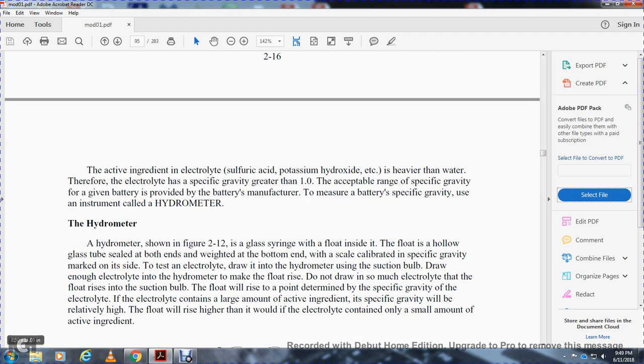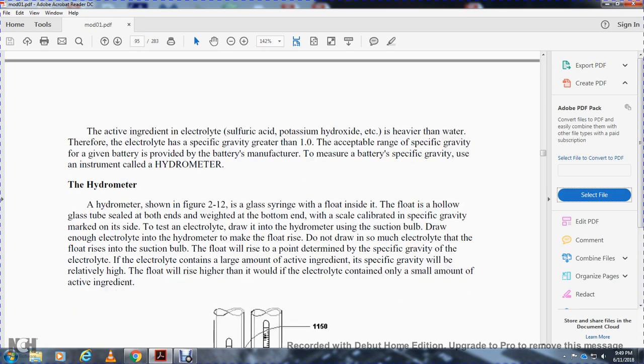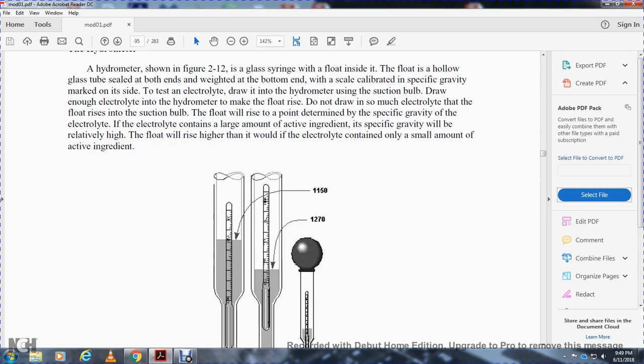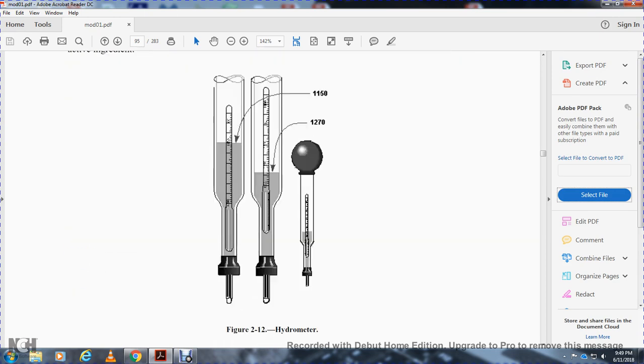The hydrometer is a glass syringe with a float inside a glass tube, weighted at the bottom with a scale calibrated in specific gravity on the side. To test the electrolyte, use the suction bulb to draw enough electrolyte into the hydrometer to make the float rise — but do not draw so much that the float rises into the suction bulb. The float rises to a level that determines the specific gravity of the electrolyte. If the electrolyte contains a larger amount of active ingredient, the specific gravity will be relatively high and the float will rise higher.